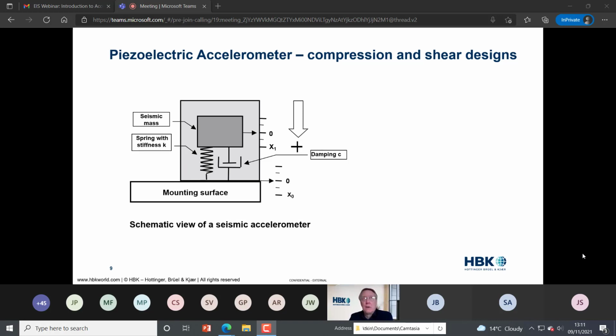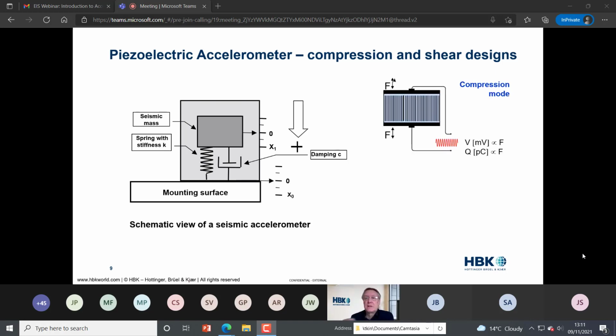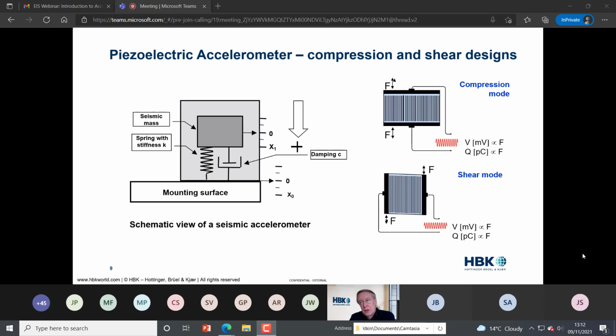If you do have some compliance and not a perfect connection there, you will be introducing another mass spring damper, which will have an effect upon the frequency response. Now, there are two ways, broadly speaking, in which the ceramic material can be arranged. If you've got the seismic masses top and bottom of the piezoelectric disc, then that is what we call compression mode. If you mount the masses on either side so that you're putting a shear force into the crystal, then that is called a shear design. And those are the two main technologies still today.